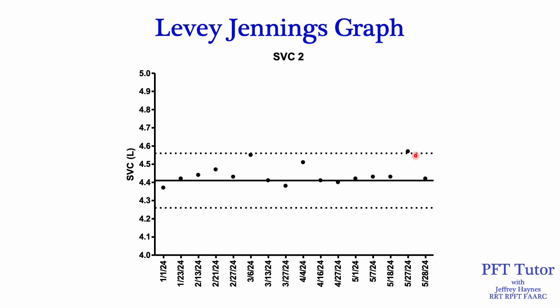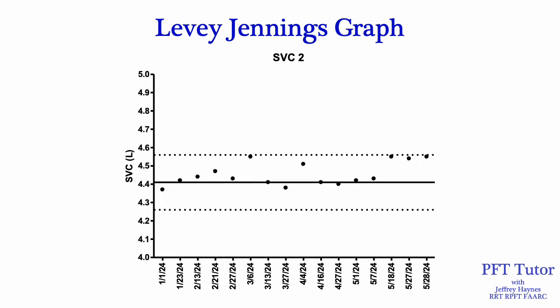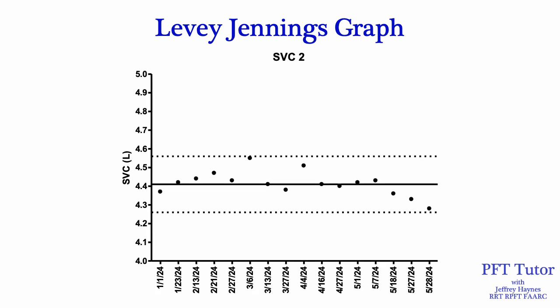A Levey-Jennings graph lets you identify a random error just outside of the 2 standard deviation range — keeping in mind that even when things are operating correctly, 1 in 20 measurements might be slightly out of that range. It also allows you to identify a shift — data points that have shifted from previous measurements may indicate a change in system function even though values haven't fallen outside the normal range. You can also identify trends where numbers are progressively falling, which can indicate a developing problem.